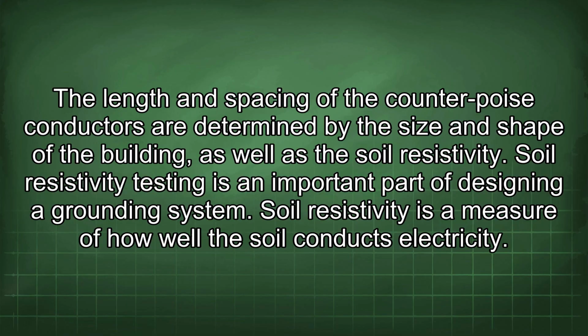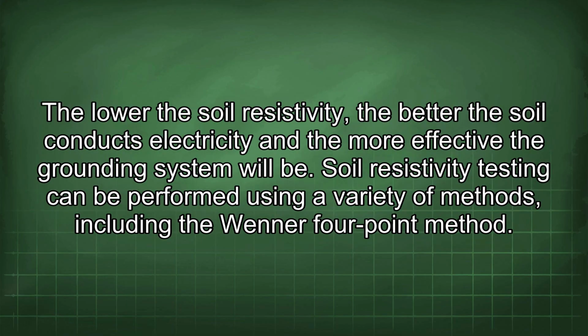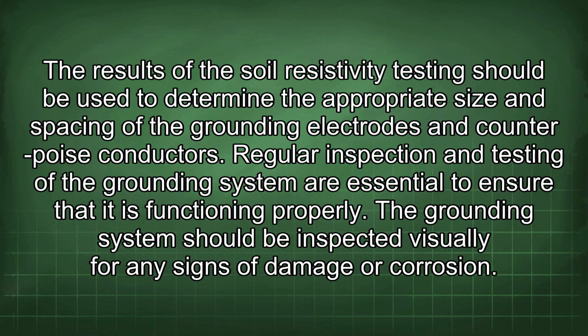Soil resistivity testing is an important part of designing a grounding system. Soil resistivity is a measure of how well the soil conducts electricity. The lower the soil resistivity, the better the soil conducts electricity and the more effective the grounding system will be. Soil resistivity testing can be performed using a variety of methods, including the Wenner 4-point method.